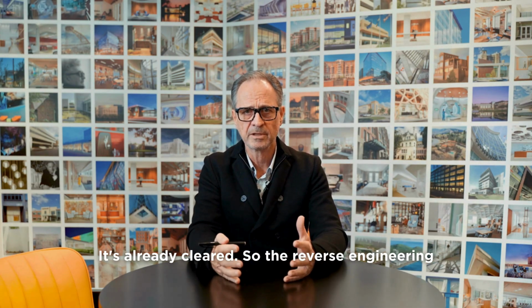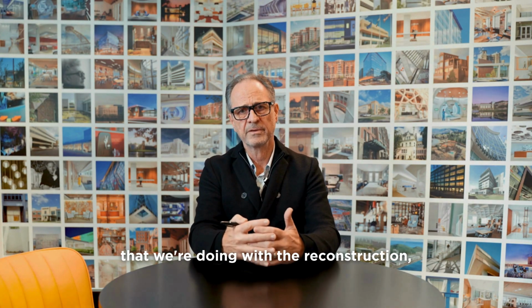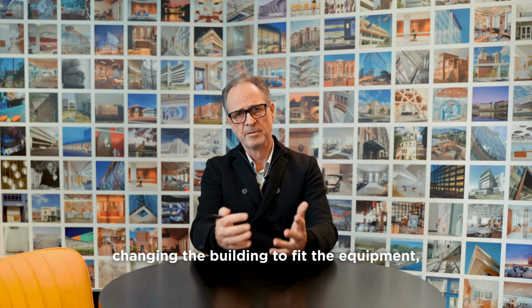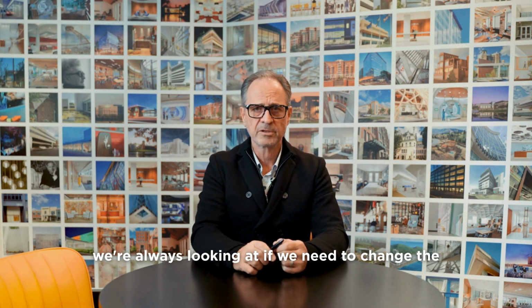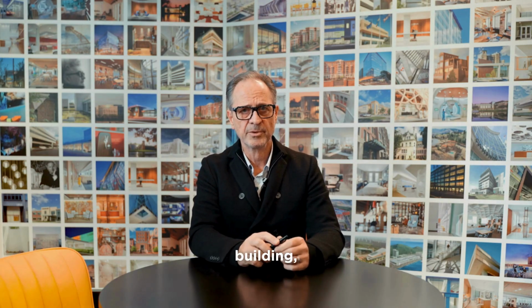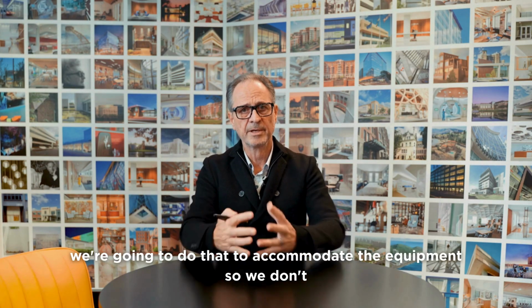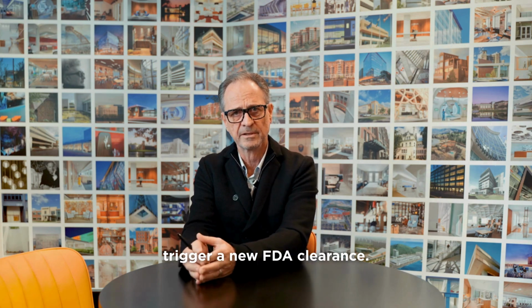It's already cleared. So with the reverse engineering we're doing in the reconstruction, changing the building to fit the equipment, we're always looking to change the building rather than the equipment, so we don't trigger a new FDA clearance.